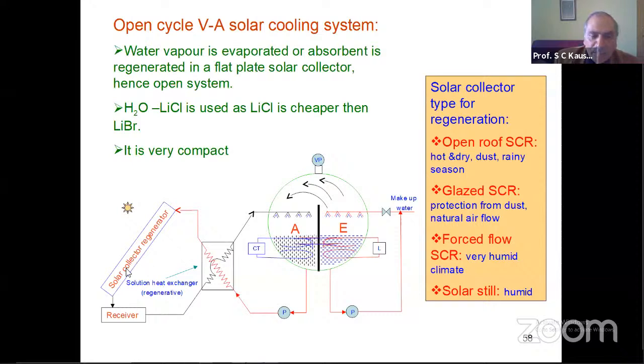Now, based on this system, a building is being cooled in Moscow. I have visited that place where the building roof is being used as the solar collector regenerator, and this absorber evaporator assembly was installed in the wall. The interior of the wall is coupled with this evaporator, and the exterior of the wall was this absorber chamber. It is cooled by the cooling tower. So the building is being cooled through this evaporator coil, and the cooling tower is connected with the absorber. And the roof of the building was acting as a solar collector regenerator. So this system is most suitable for providing a large scale solar cooling option. Large scale solar cooling can be provided by using this open cycle vapor absorption cooling.